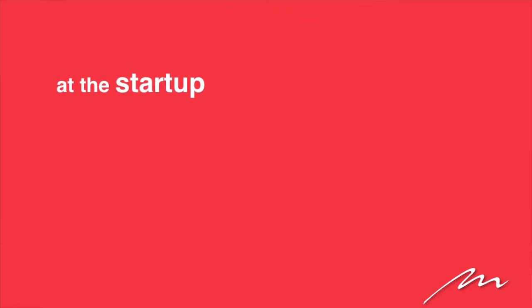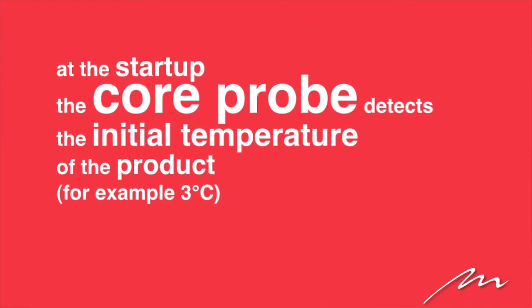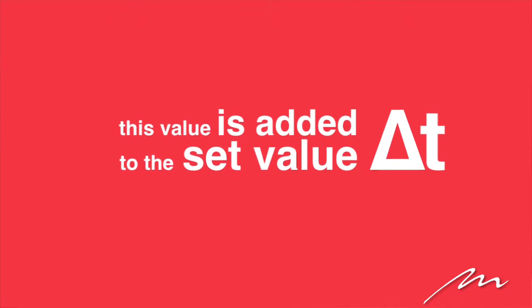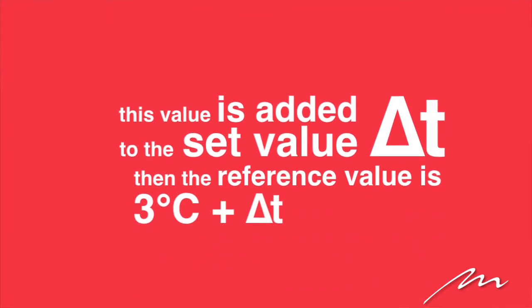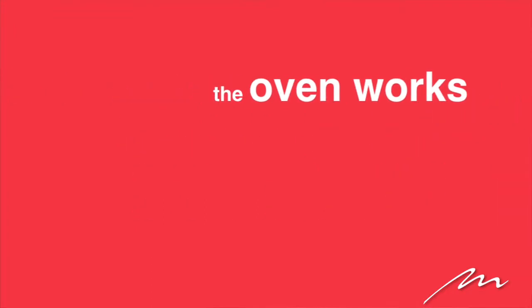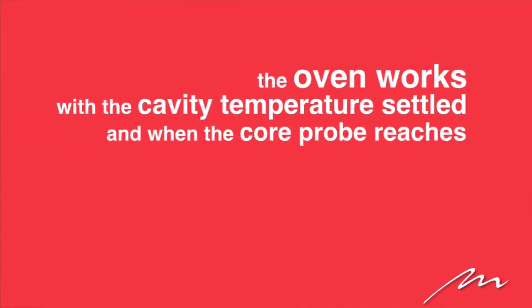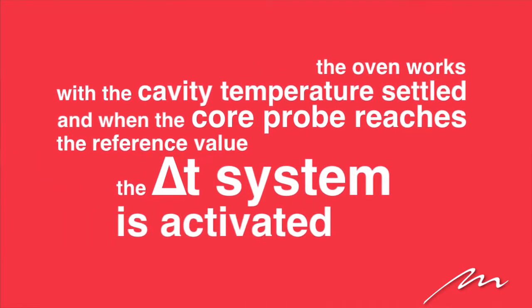At startup, the core probe detects an initial temperature of a product, for example, +3 degrees when it's just removed from the cold room. This value is added to the set value delta T, and the reference value of delta T is 3 plus 30 degrees equals 33. The oven works with the cavity temperature settled, and when the core probe reaches the reference value, 3 degrees plus delta, the system is activated.